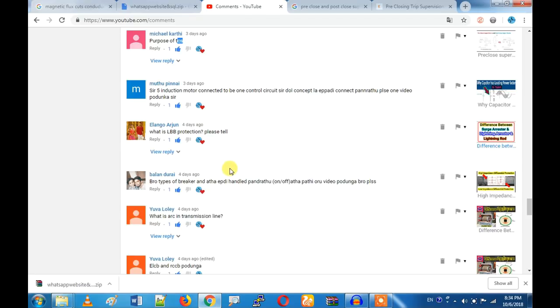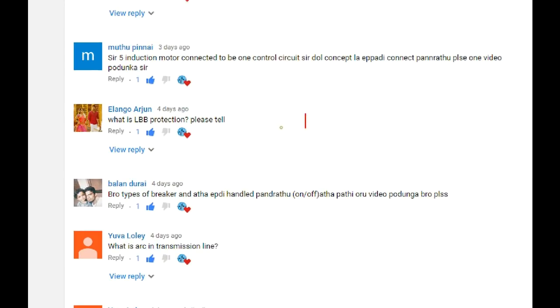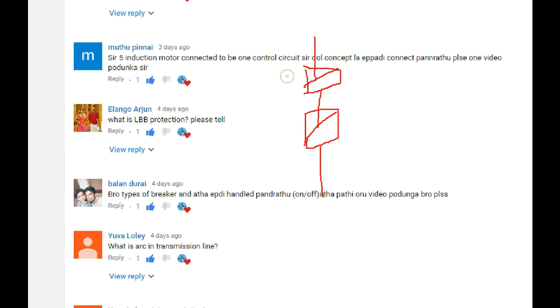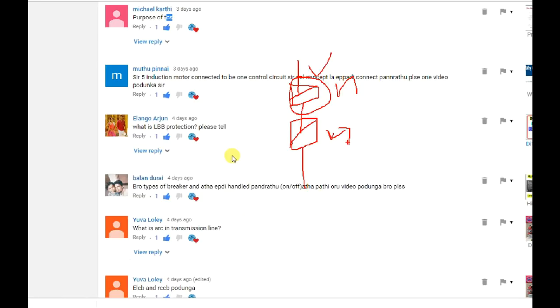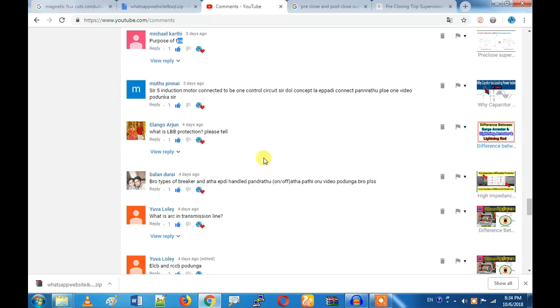What is LBB protection? LBB is local breaker backup protection. For example, if you have two breakers — a synchronized breaker and a grid breaker, or a gen breaker — with a generator in synchronized condition: if there is a fault, the first trip is the gen breaker. If the gen breaker trips, then the grid breaker operates. That is local breaker backup protection — the DG breaker is the local breaker.